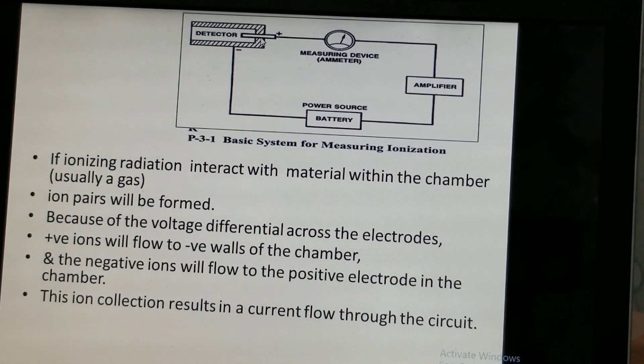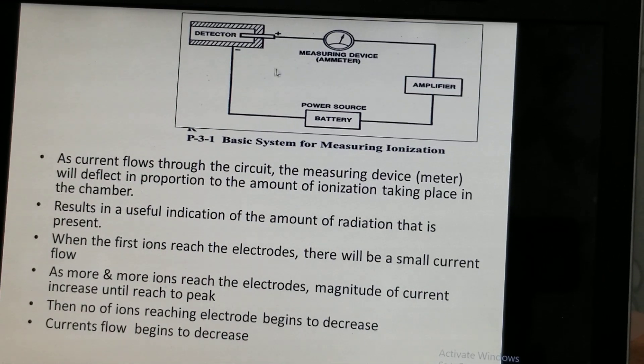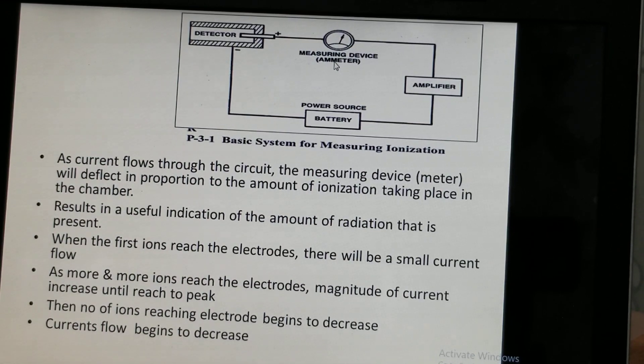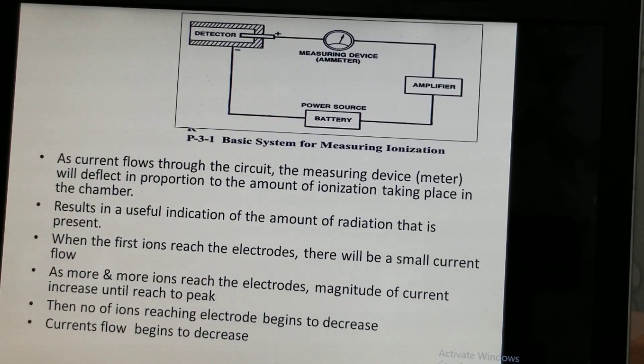When current flows through the circuit, the measuring device — the meter — deflects in proportion to the amount of ionization that takes place in the chamber. As a result, we get a useful indication of how much radiation is present in that area. When the first ions reach the electrodes, there is a small current flow.